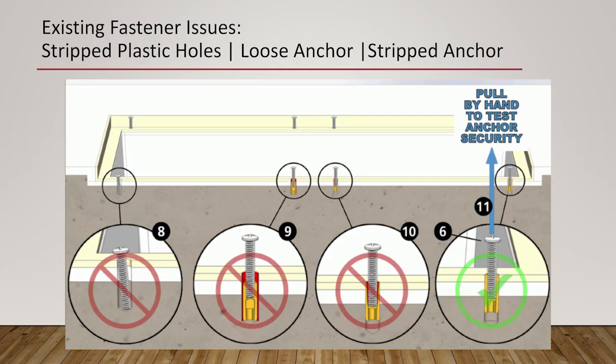So now one of the other elements that Ray talks about is fastener integrity. And so this is a big challenge for the contractors, the people actually doing this installation, where we take a drain cover off and go to put a replacement in its place. Well, we have to use the screws that came with the manufacturer. But if you have a cover that's designed for threaded inserts, brass threads, and they're pulled out of the plastic grate, it's not going to work. So they can't install that grate unless the manufacturer provides a way to handle it.